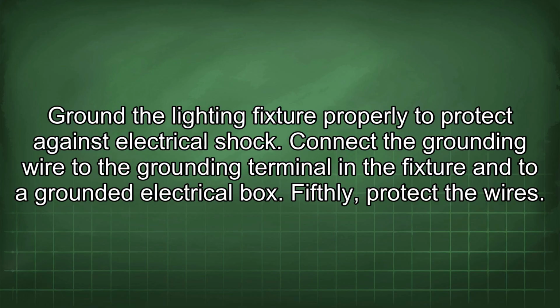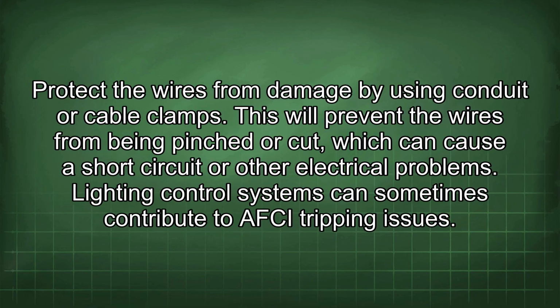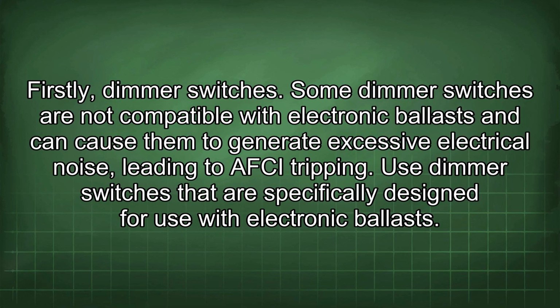Fifthly, protect the wires. Protect the wires from damage by using conduit or cable clamps. This will prevent the wires from being pinched or cut, which can cause a short circuit or other electrical problems. Lighting control systems can sometimes contribute to AFCI tripping issues. Firstly, dimmer switches. Some dimmer switches are not compatible with electronic ballasts and can cause them to generate excessive electrical noise, leading to AFCI tripping. Use dimmer switches that are specifically designed for use with electronic ballasts.